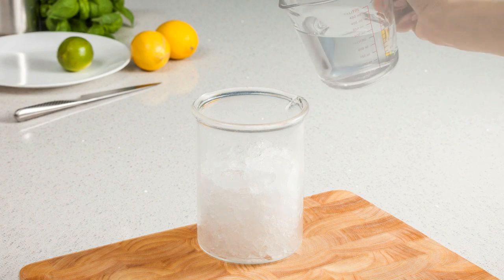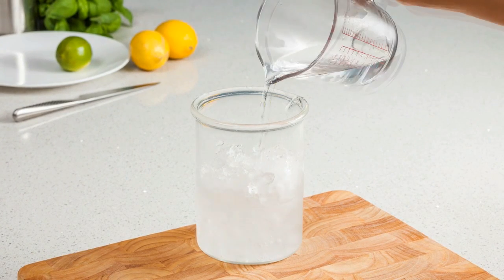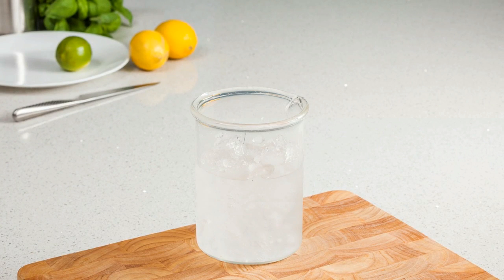Once the container is full, pour in cold water until the surface starts to turn from ice white to slightly grey in colour. The ice on the surface should show just a small amount of water and not an excessive amount. So push down firmly on the ice and pour off any excess. Essentially, the ice should not be allowed to float. Your ice point is now ready for use and can be topped up as necessary, depending on how long it's needed. Simply add more ice, but remember to drain any excess water.